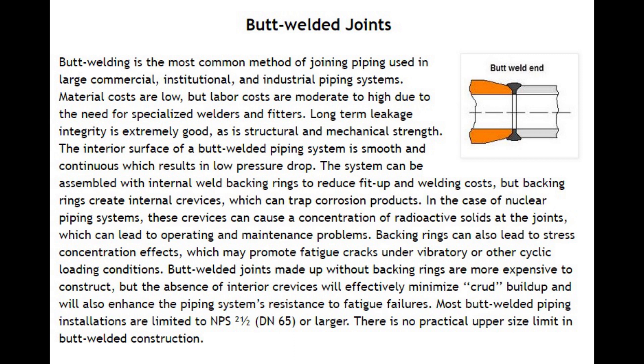The interior surface of a butt welded piping system is smooth and continuous, which results in low pressure drop. The system can be assembled with internal weld backing rings to reduce fit-up and welding costs, but backing rings create internal crevices which can trap corrosion products. In the case of nuclear piping systems, these crevices can cause a concentration of radioactive solids at the joints.